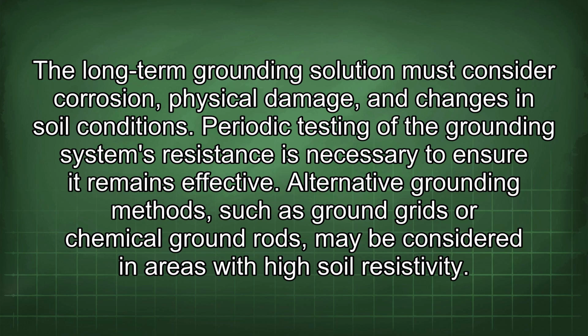Periodic testing of the grounding system's resistance is necessary to ensure it remains effective. Alternative grounding methods, such as ground grids or chemical ground rods, may be considered in areas with high soil resistivity.